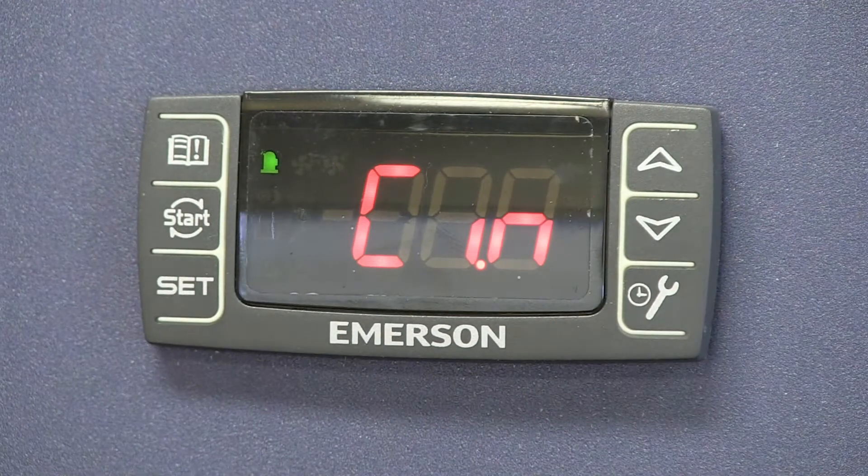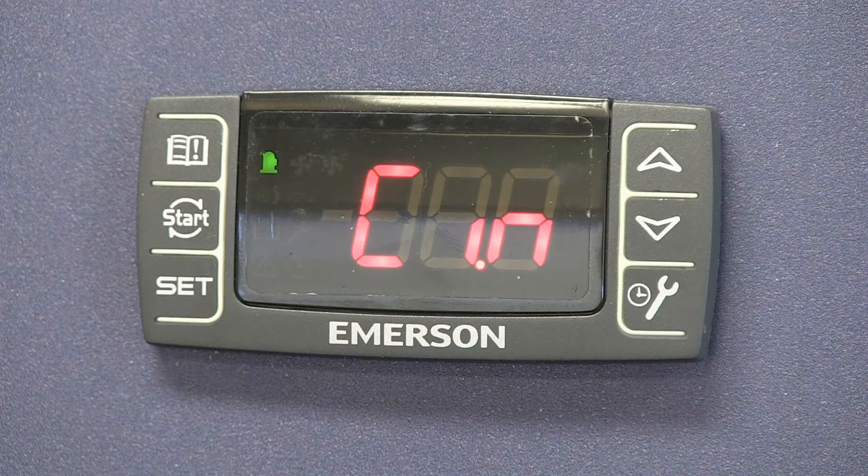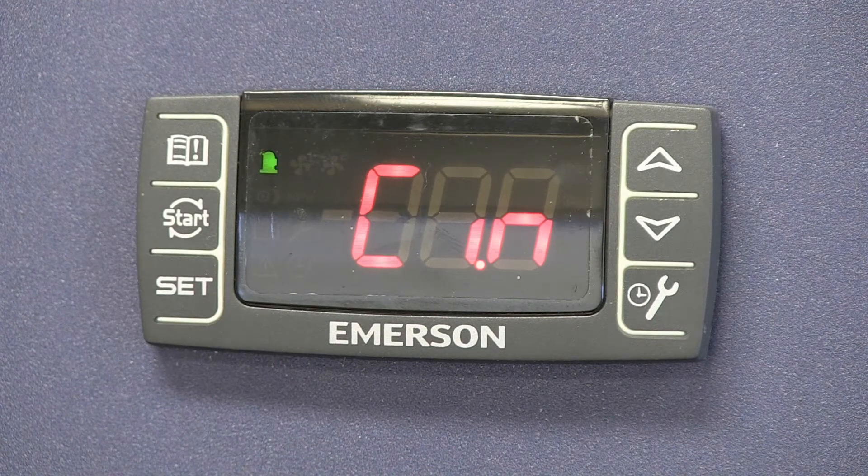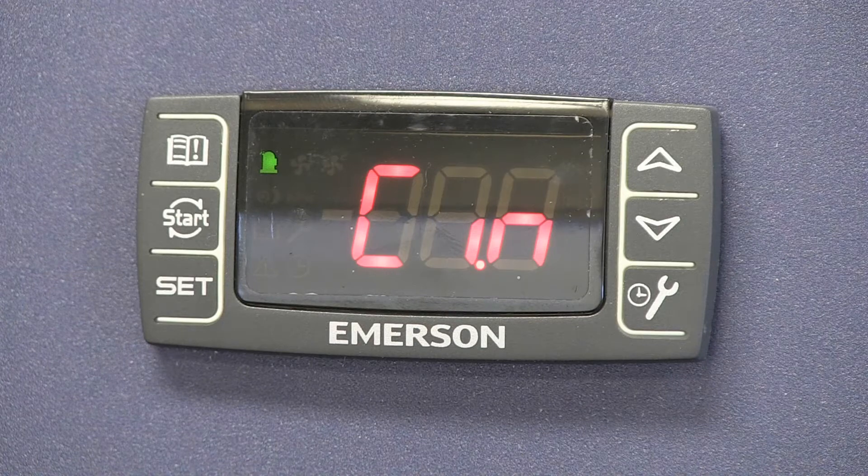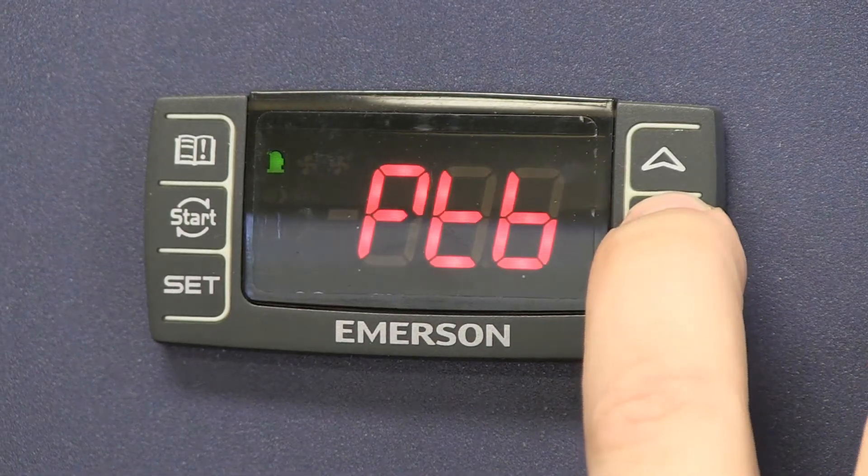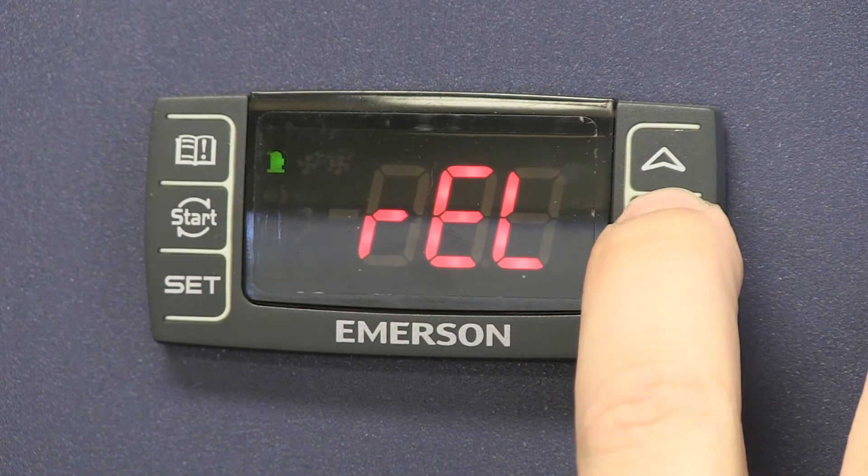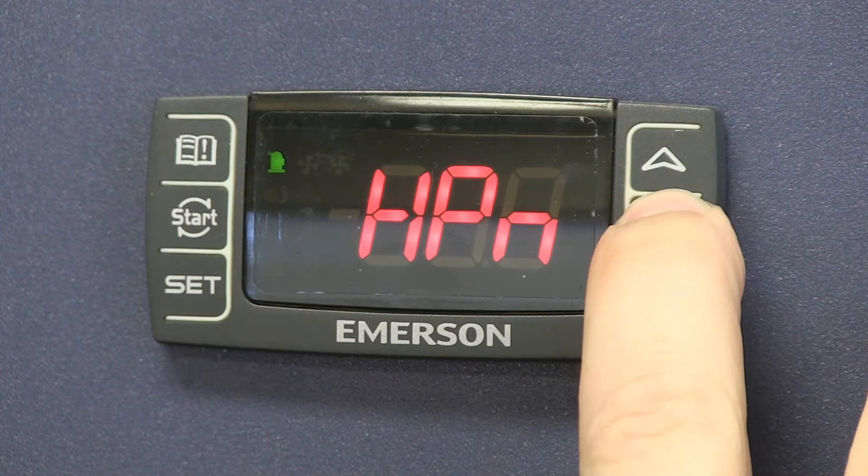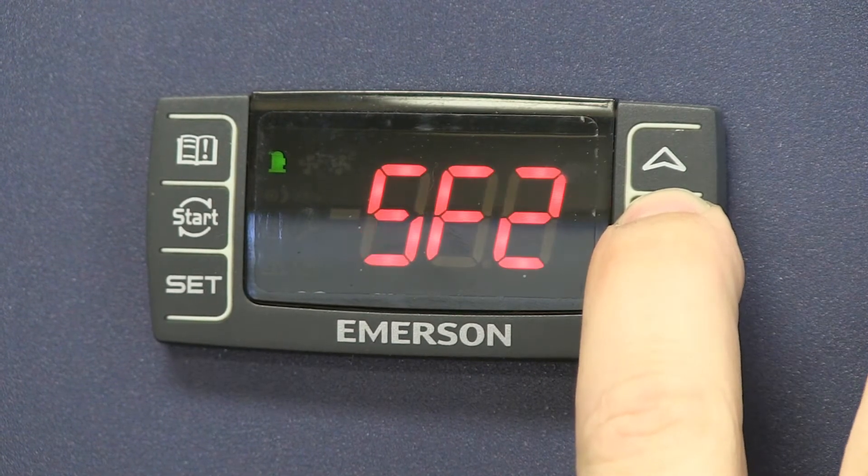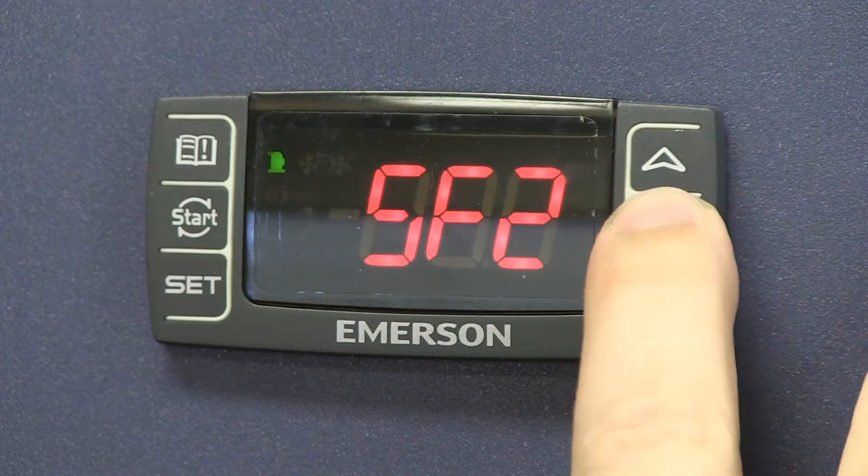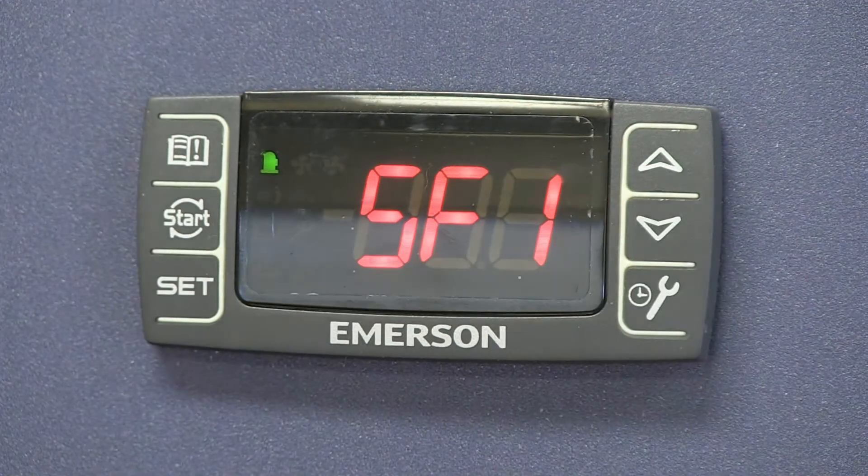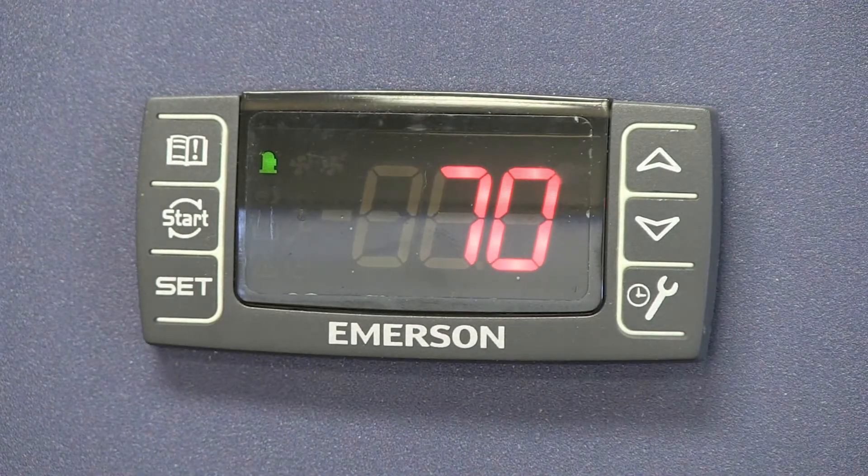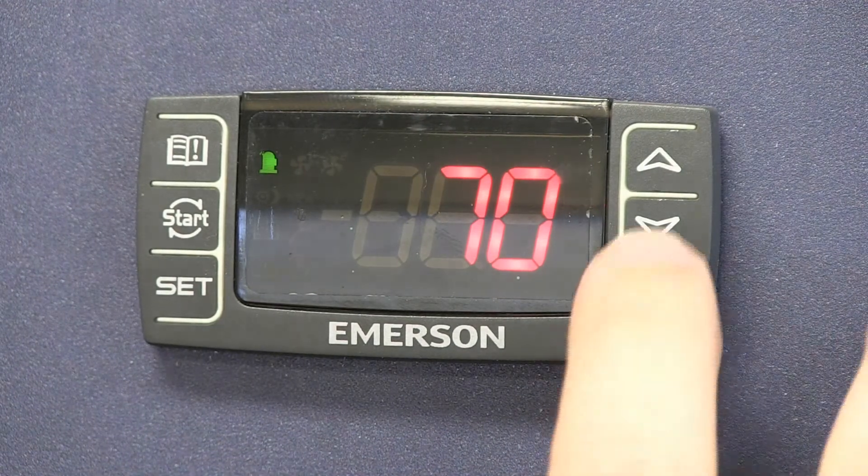Now we're in the level two menu. To control the fans, the first parameter that we want to get to is the SF1 parameter. This is the cutout set point for the first fan. So there at SF1, we'll hit set and you'll see that this is set at 70 degrees.